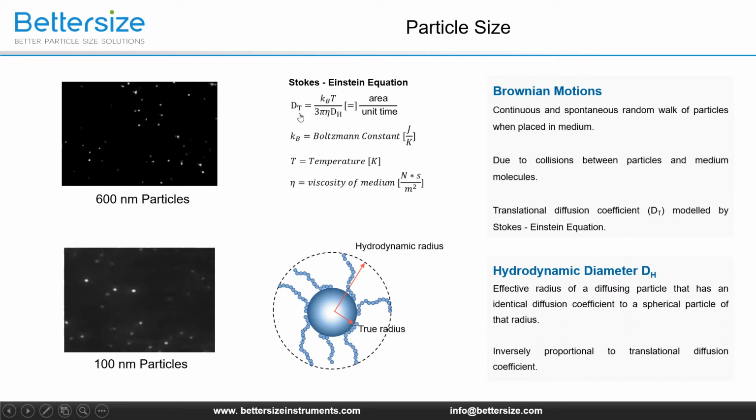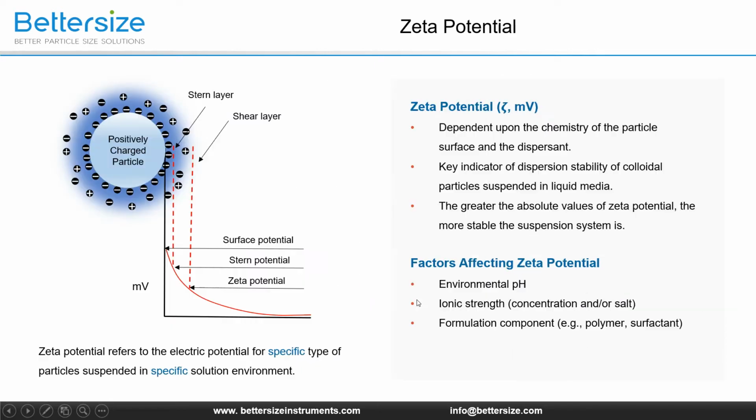Therefore, the relationship between the diffusion coefficient and the particle size can be used to calculate the particle size of the sample through the Stokes-Einstein equation. The DLS technique utilized in the BNano 90 Zeta can obtain the equivalent particle size through the hydrodynamic behavior of the particles. In other words, the measured particles and the equivalent spheres have the same diffusion behavior, namely Brownian motion.